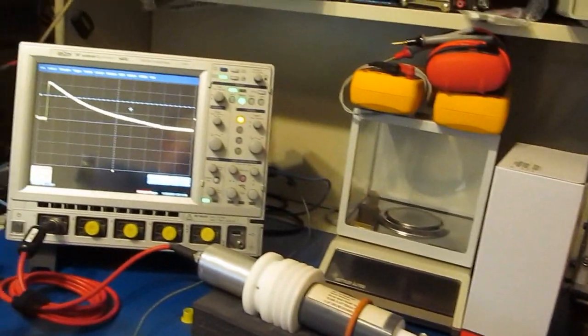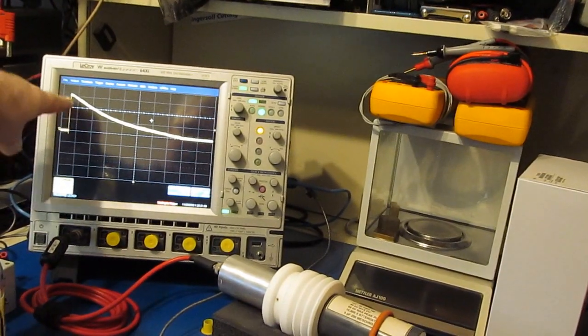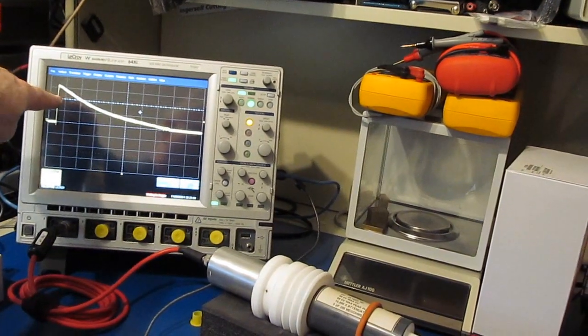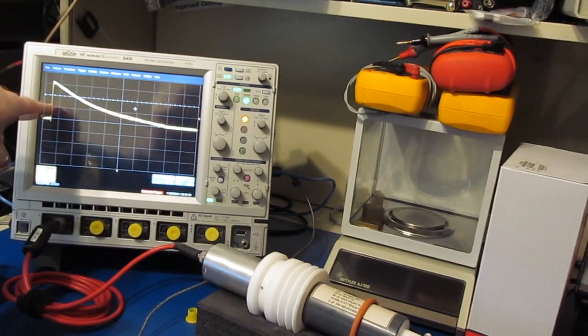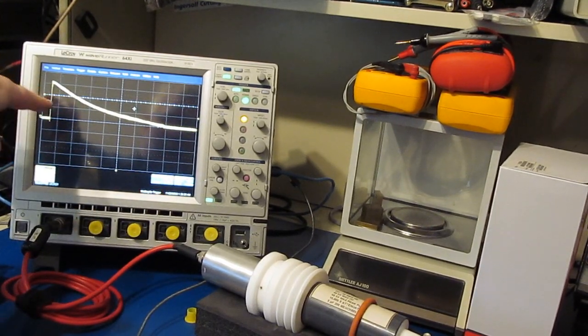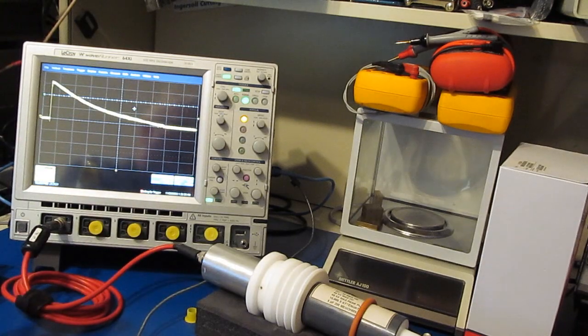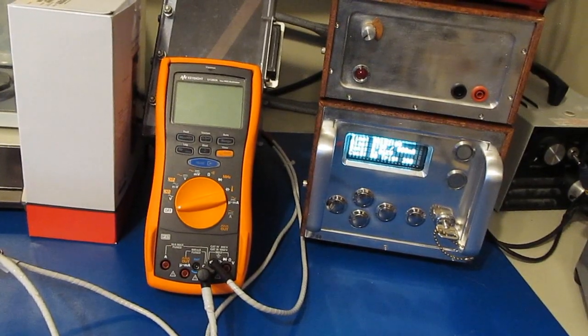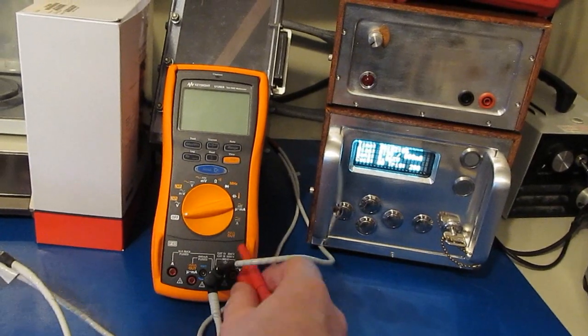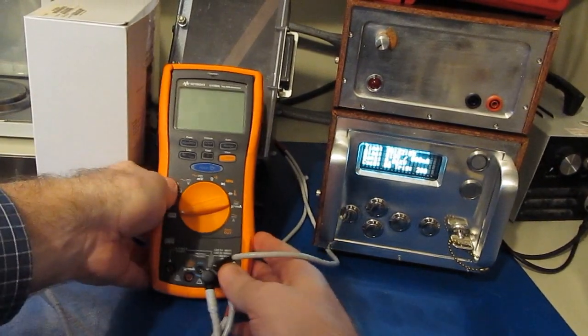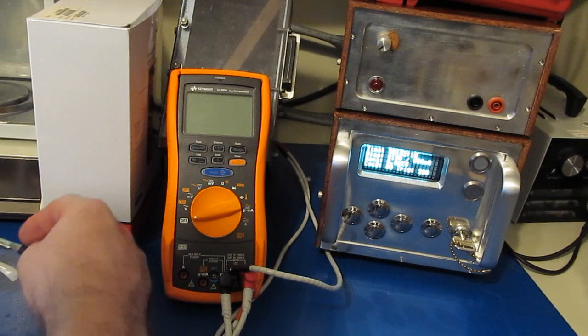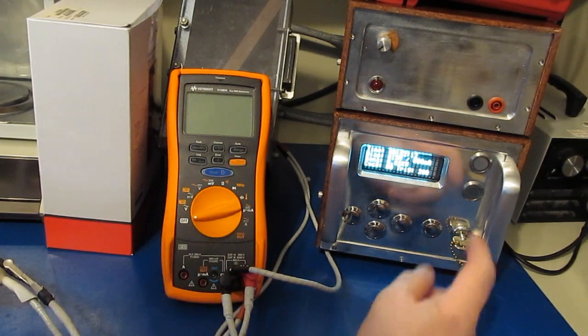So I've changed our generator. You can see we are now 3 divisions up, or 1,500 volts peak. And again, our full width half height is 2 divisions over, or 100 microseconds. And just like before, we'll be applying 5 transients, both positive and negative, with the meter set to each mode. Alright, here we go.